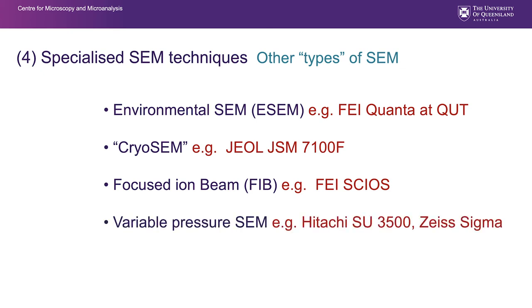Variable pressure SEM is worth spending a little more time on. It uses the same types of processes as the environmental SEM but doesn't go quite as far. It allows us to control the pressure in the chamber and use positive ions to remove charge from the sample, enabling fairly high accelerating voltages on samples that are normally insulating and very difficult to image otherwise. This allows micro-analysis requiring those high KVs.